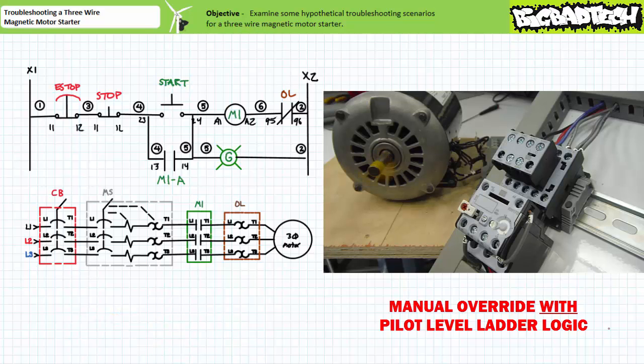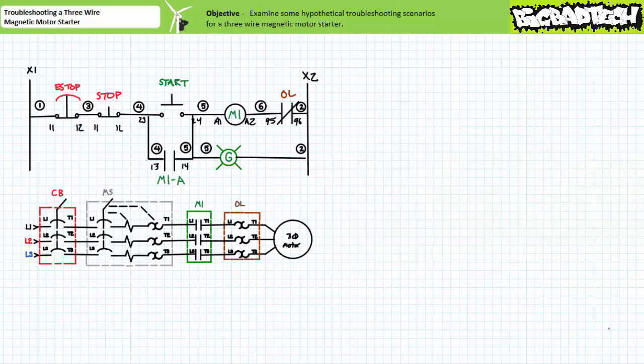Recall that the movement of the contact carrier closes not only the primary power contacts, but also the auxiliary pilot level contacts associated with this particular contactor. Notably the M1A holding contact. The holding circuit is established and given pilot level ladder logic is functional, the holding circuit maintains the last asserted state.